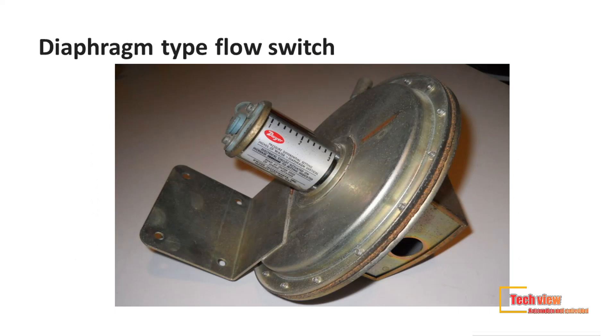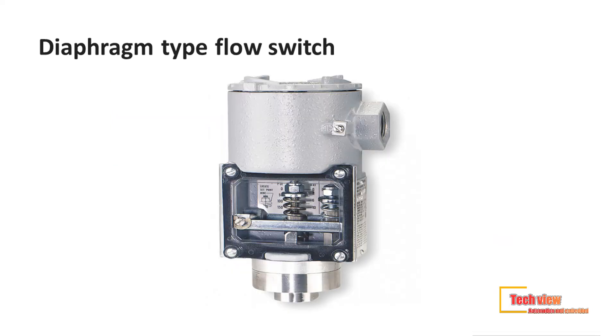The next type is the diaphragm type flow switch. In construction, diaphragm type flow switches are similar to DP switches. The only difference is that there is a gap that allows fluid to flow through the transition between the inlet and the outlet port, while it is completely closed in DP switches.